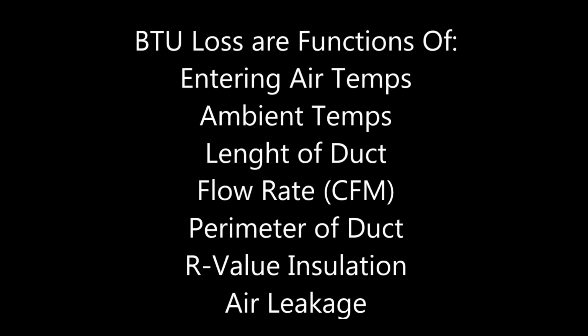So heat losses, or delta T losses, are a relationship between the air entering the ductwork, the ambient temperature, the length of the duct, the flow rate, otherwise known as the CFM, the perimeter of the duct, the R value, and the air leakage. Well, there you have it. These are my results.